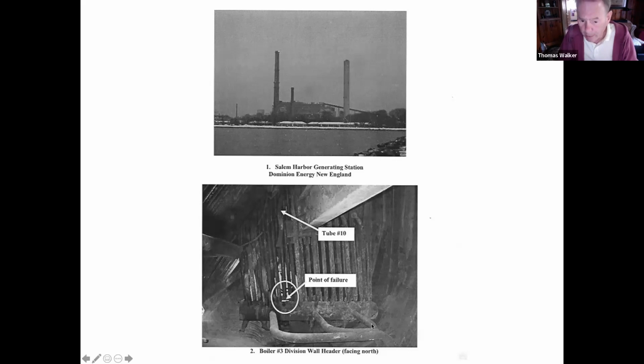If you were to operate these blowdown valves while there's a fire in the boiler, that temporary disruption of flow in these tubes could cause them to overheat and could cause damage. So the only blowdown valves that you and I will operate are the bottom blowdown valves, which are on the mud drum, like you said. But appreciate that the water walls will have separate headers. That makes sense?